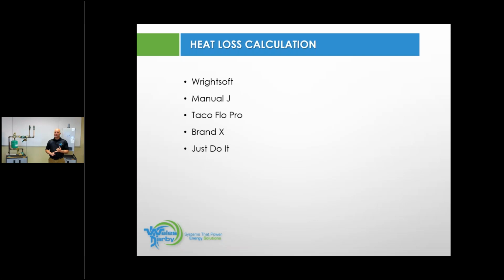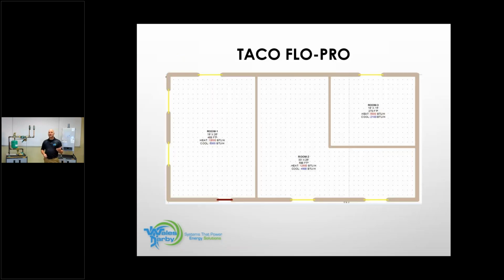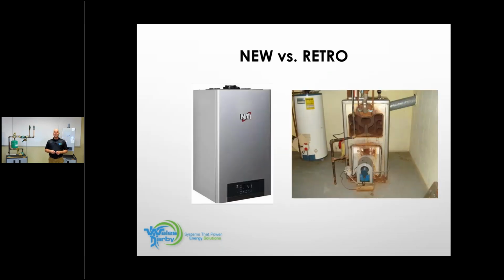What improvements have been done to the home? There are a lot of things that go into new and/or replacing. This is just a diagram of Taco's program, Flo-Pro. Again, we don't care which one you use. We just want to make sure that it meets the needs of the end user, the homeowner. So new and/or retrofit. We have condensing on the left here and cast iron on the right. On jobs like this, do I replace that with a condensing product, or do I go back in there with a cast iron product?